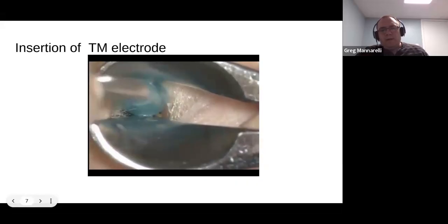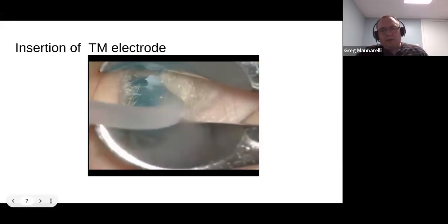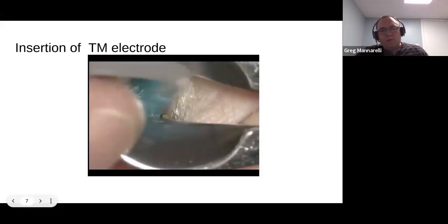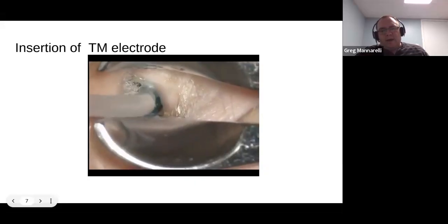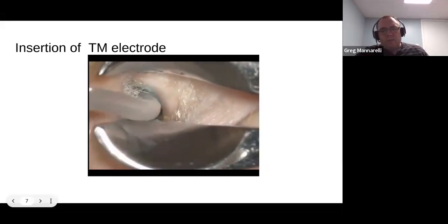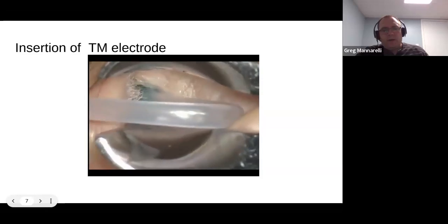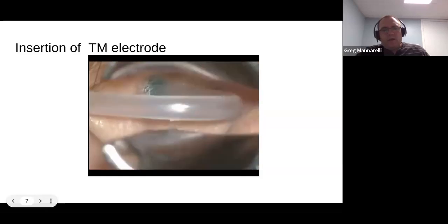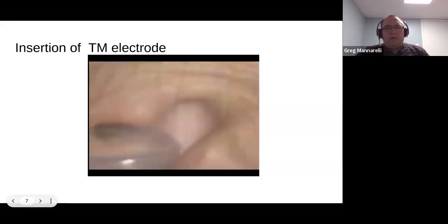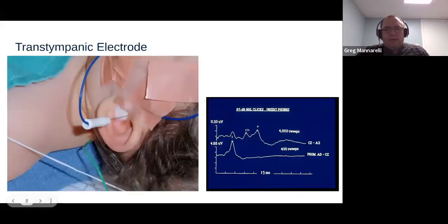With someone with a smaller ear canal, it can sometimes be hard to see past your electrode when going in, but you're going to basically work it past the canal, set it down on the eardrum, and apply a little pressure to the tube to keep it on there while you remove your speculum. Then you'll squish up an insert earphone, put it down in the canal, deliver your sound stimulus, and then proceed to do your testing.